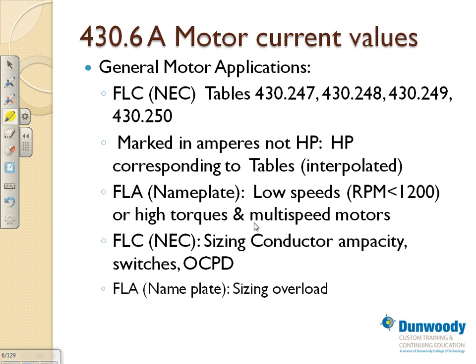You're going to go to the tables based on the voltage, and you're going to find the equivalent horsepower of that motor. It's easy. If it's a 100 amp motor, I can go to the table, go to which voltage is 480, so that will be 460. Keep going until you hit 100. If you can't find 100, you can find 90 and see 120. You're going to go to the next one, and you go across, and you find the amps of the horsepower of that motor.